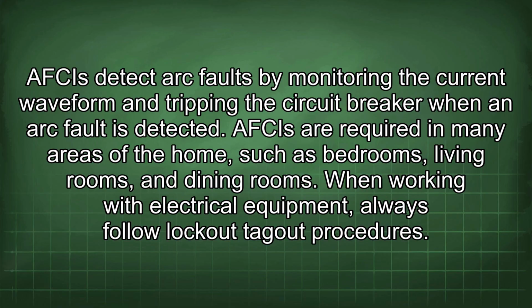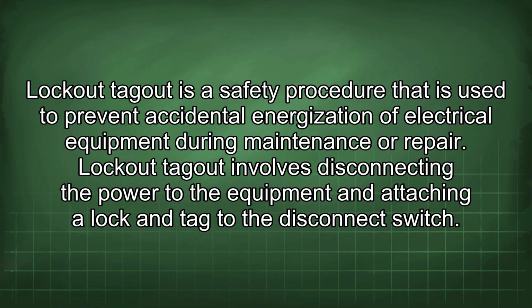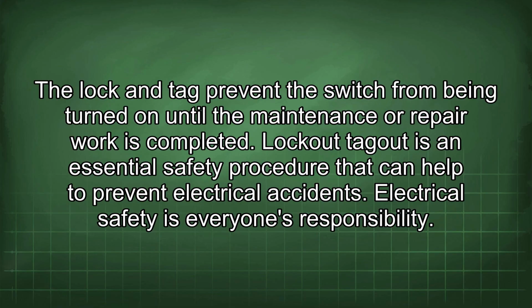When working with electrical equipment, always follow lockout-tagout procedures. Lockout-tagout is a safety procedure that is used to prevent accidental energization of electrical equipment during maintenance or repair. Lockout-tagout involves disconnecting the power to the equipment and attaching a lock and tag to the disconnect switch. The lock and tag prevent the switch from being turned on until the maintenance or repair work is completed. Lockout-tagout is an essential safety procedure that can help to prevent electrical accidents.